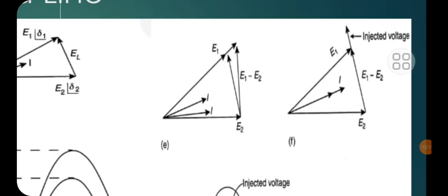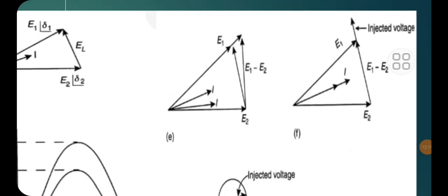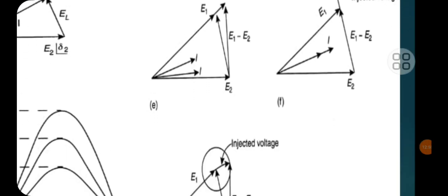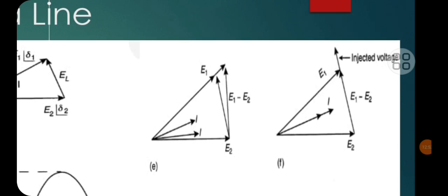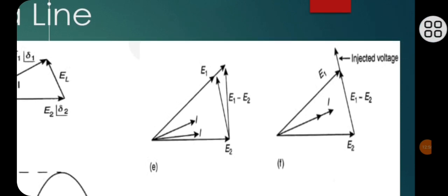And the vector diagram E here shows the injection of an increase in the bus voltage E1, which results in changing the orientation of the vector E1 minus E2. Consequently, the current vector I also changes its orientation. So it shows that when you change a bus voltage, whether it is E1 or E2, you cause a change in reactive power flow, not much change in active power. You also see the phasor diagram F here, where a voltage is injected in series with the line, E1 minus E2.